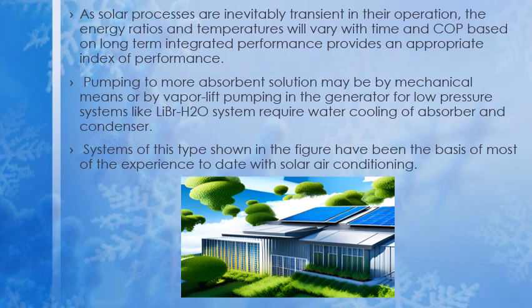As solar processes are inevitably transient in their operation, the energy ratios and temperatures will vary with time, and COP based on long-term integrated performance provides an appropriate index of performance. Pumping of the absorbent solution may be by mechanical means or by vapor lift pumping in the generator for low pressure systems like LiBr and H2O, that is lithium bromide and water system, which require water cooling of the absorber and condenser. Systems of this type, which is shown in the figure, have been the basis of most of the experience to date with solar air conditioning.